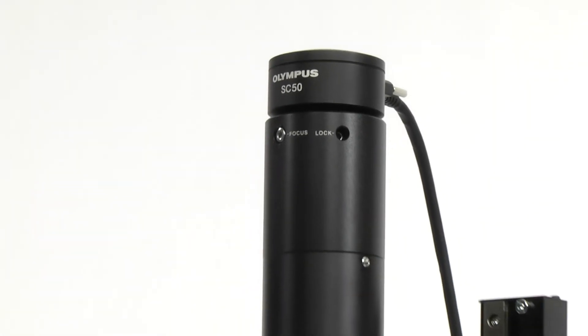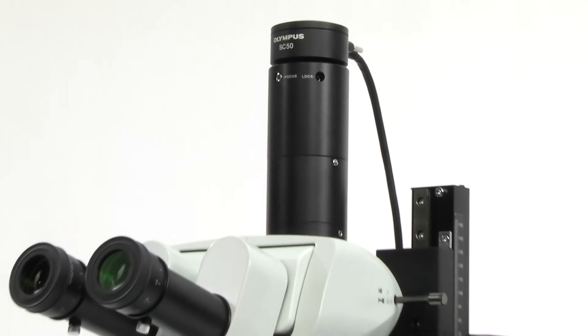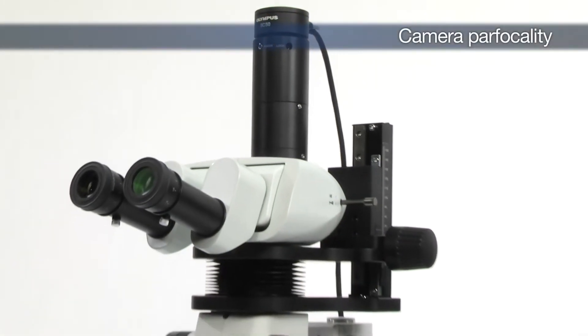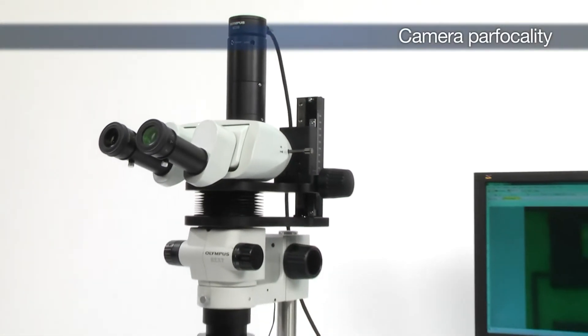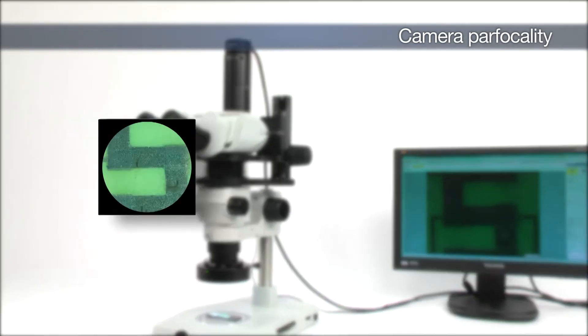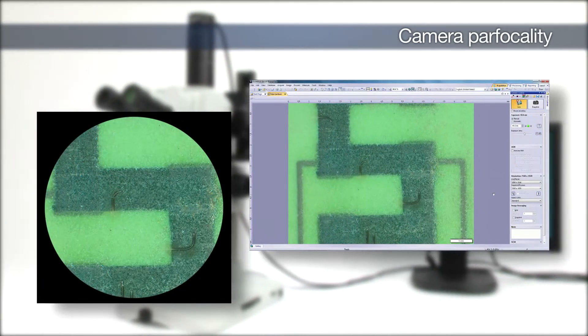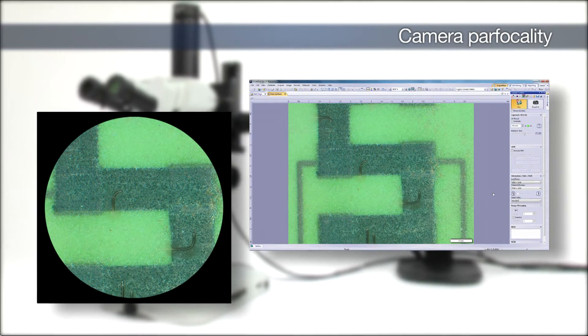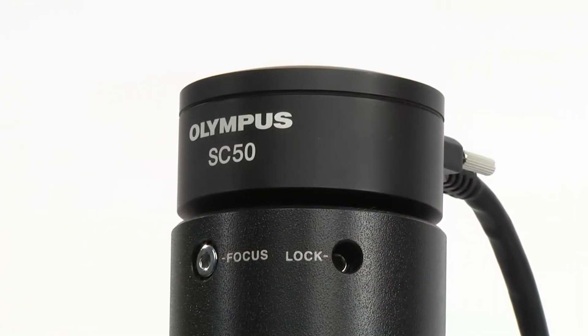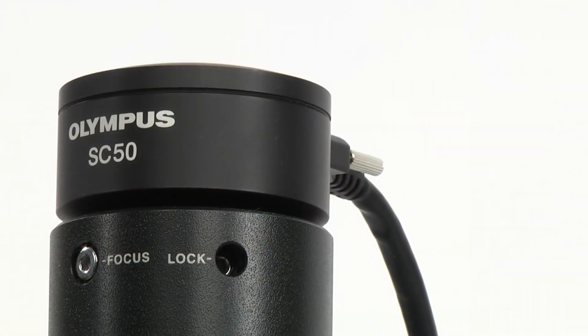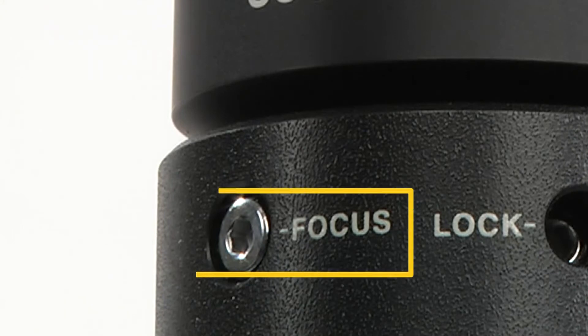For stereo microscopes equipped with digital imaging systems, proper camera parfocality is important to help ensure that the image viewed through the microscope and the image displayed on the monitor are in focus with each other. For this procedure to work, the microscope should be equipped with a camera mount that has a built-in focus adjustment.